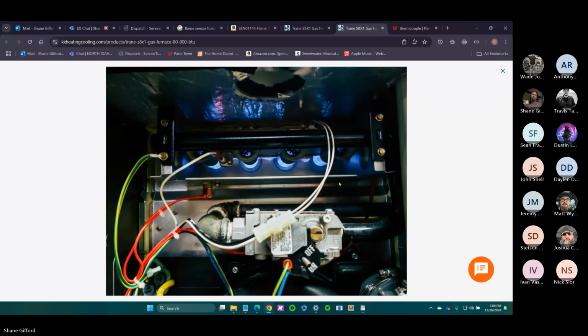We had one recently, a gas pack, that would kick on but then immediately shut off, or it would kick on and run, and then within a few minutes it would shut off. And every single time we looked at it, this rollout was popped. So it sensed flame or heat in an area that should not have been that hot and said, hey, we're that hot, shut down. And it killed everything. It immediately shuts the gas off, shuts everything off. So on this unit, you've got a rollout and then a high limit. You can't see it, but it's actually tucked up behind the gas valve. But you will see those in the airstream, usually right near the heat exchanger.